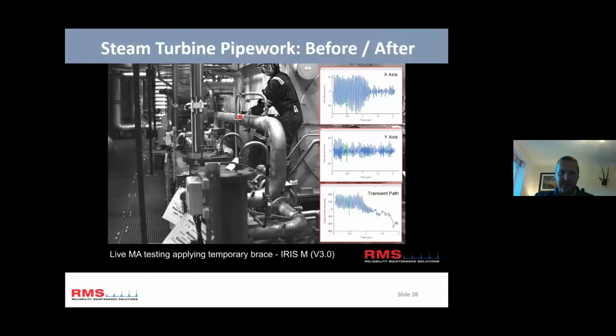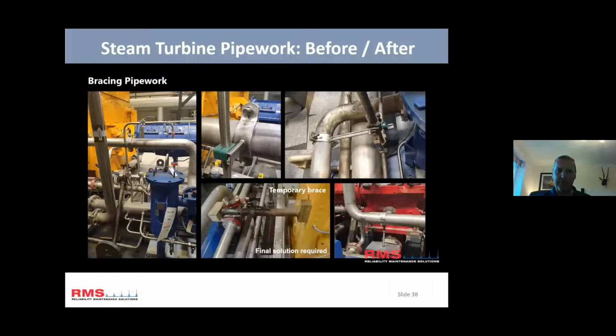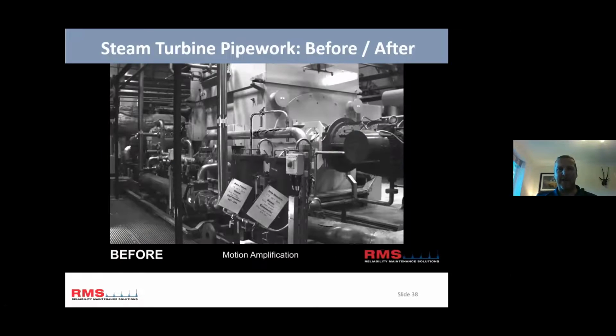This was a game changer for us using the live motion amplification. My colleague Keith is here - he's got a temporary brace against the generator, and he's tightening it up now, and you can see that vibration dropped as soon as he stiffened that pipe. So this gives you massive confidence on where you want to put the brace in, and we can test it out live. That for me is just a real game changer.